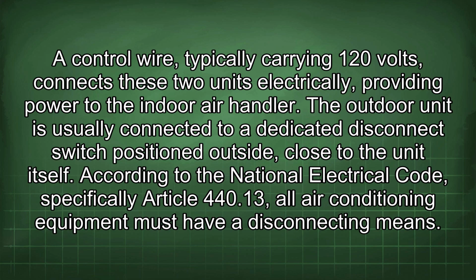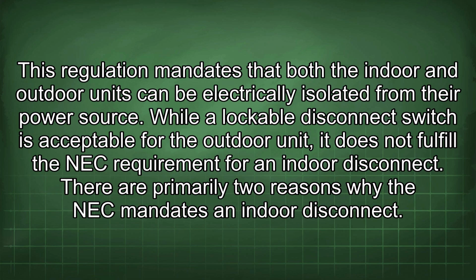The outdoor unit is usually connected to a dedicated disconnect switch positioned outside, close to the unit itself. According to the National Electrical Code, specifically Article 440.13, all air conditioning equipment must have a disconnecting means. This regulation mandates that both the indoor and outdoor units can be electrically isolated from their power source. While a lockable disconnect switch is acceptable for the outdoor unit, it does not fulfill the NEC requirement for an indoor disconnect. There are primarily two reasons why the NEC mandates an indoor disconnect.